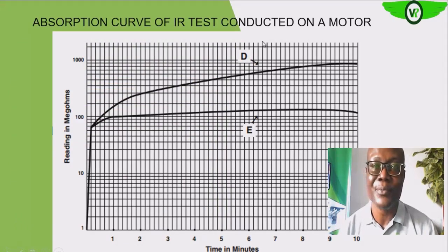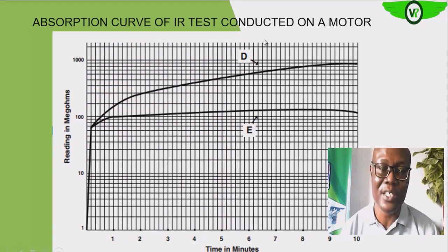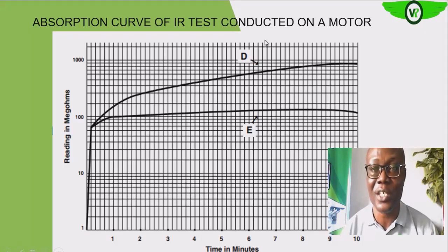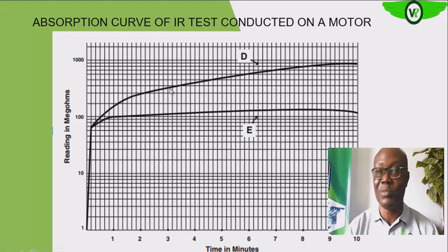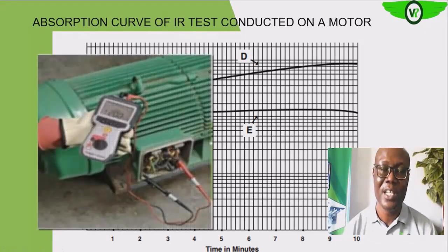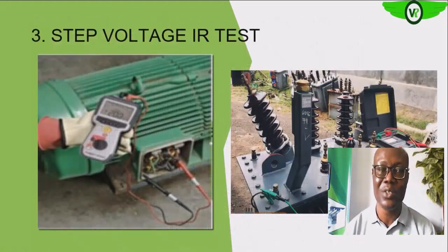So here we have the IR test of a conductor that is conducted on an electric motor. For a good insulation, this is the trend that you are supposed to have. For your first 10 minutes, see the increase like what we described before. Then when you have something like this, even though the insulation resistance reading is acceptable, you see that something is definitely wrong with the insulation. Probably moisture has been trapped or dirt has been trapped within that insulation.